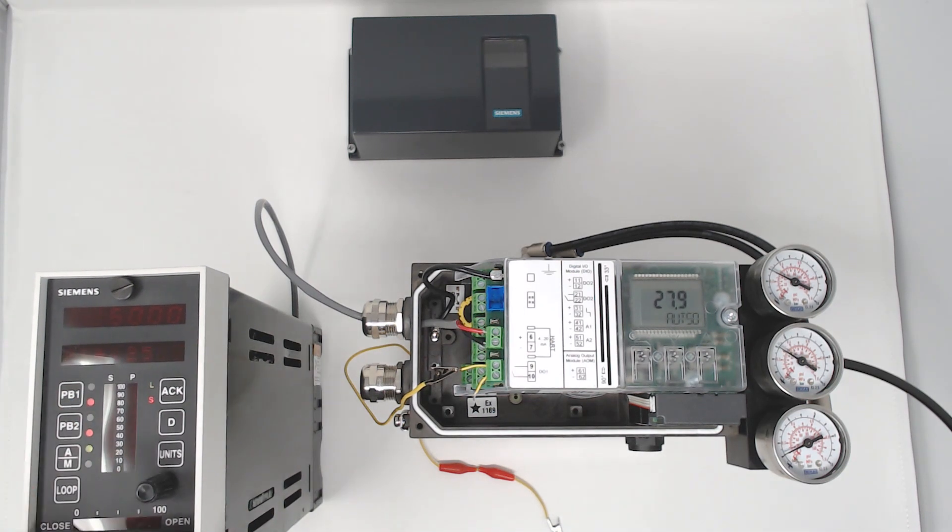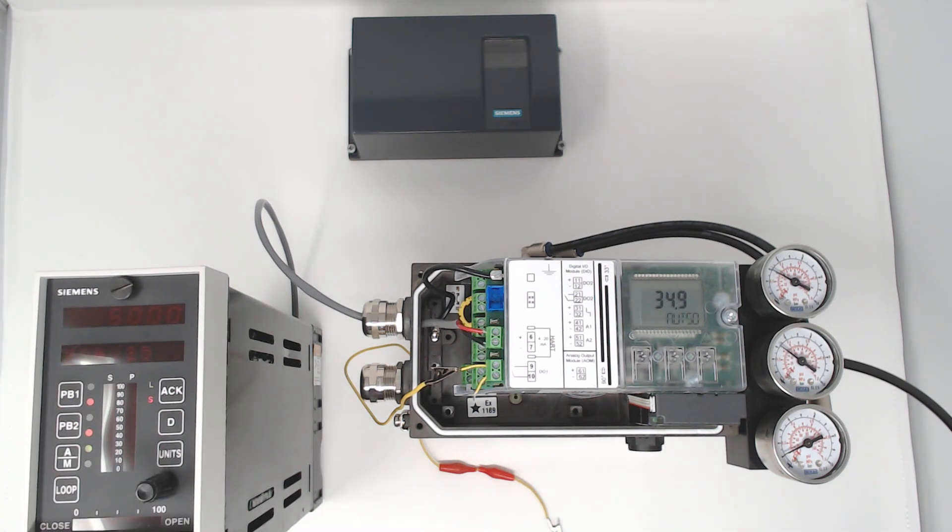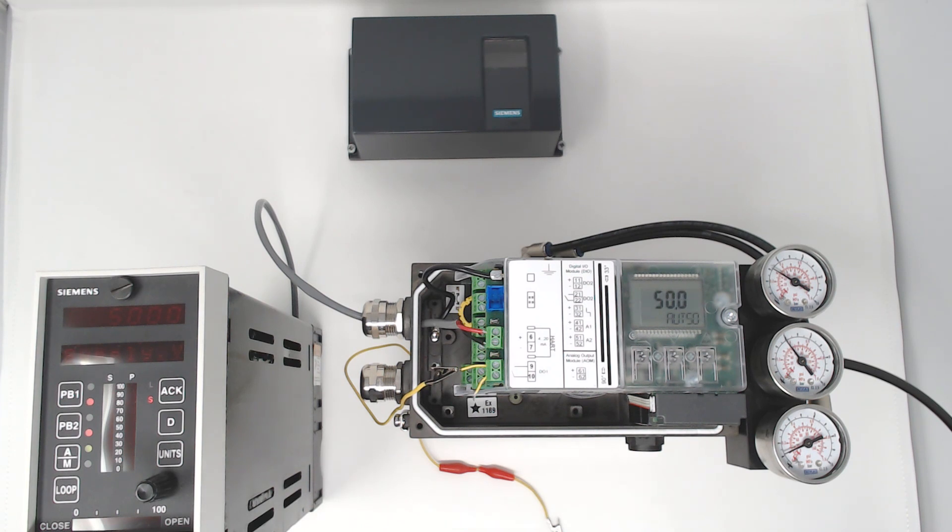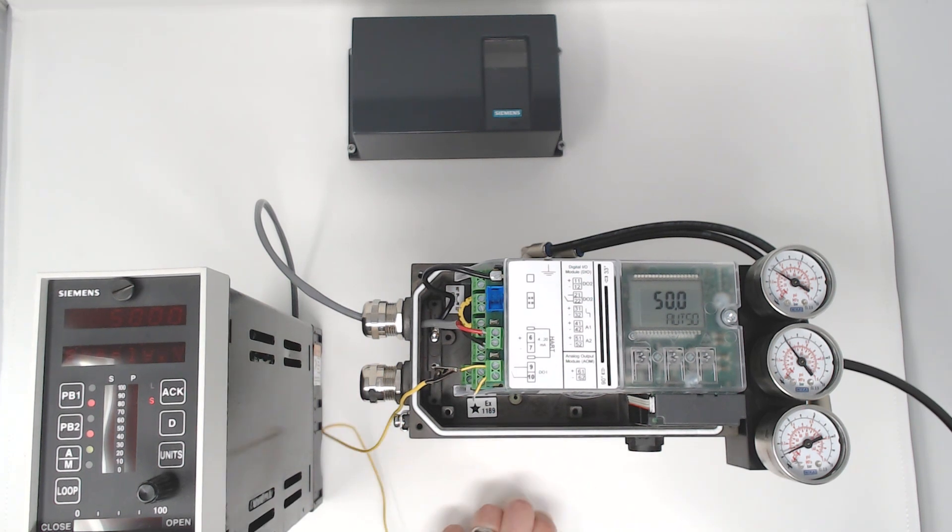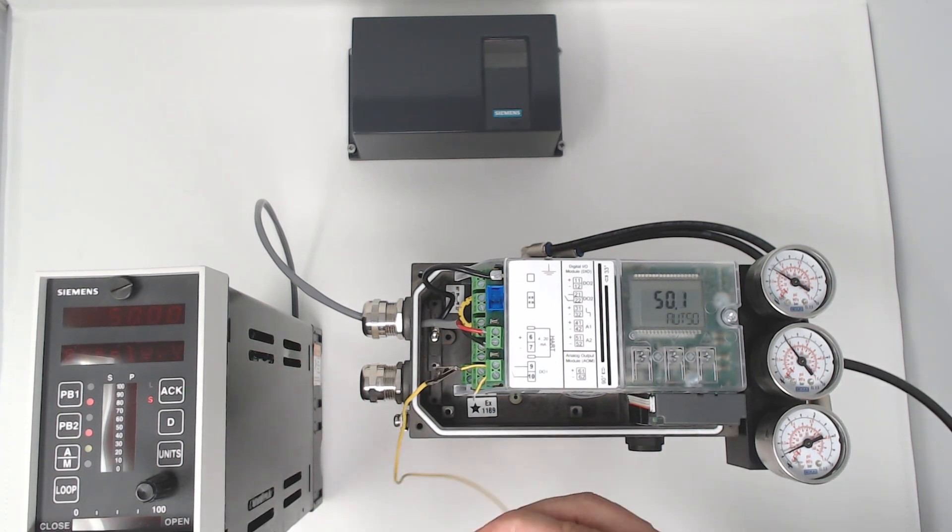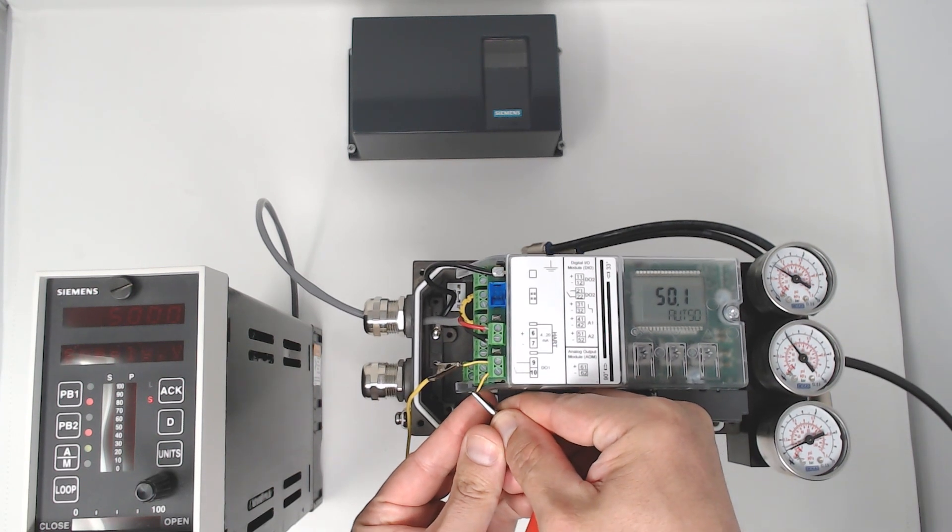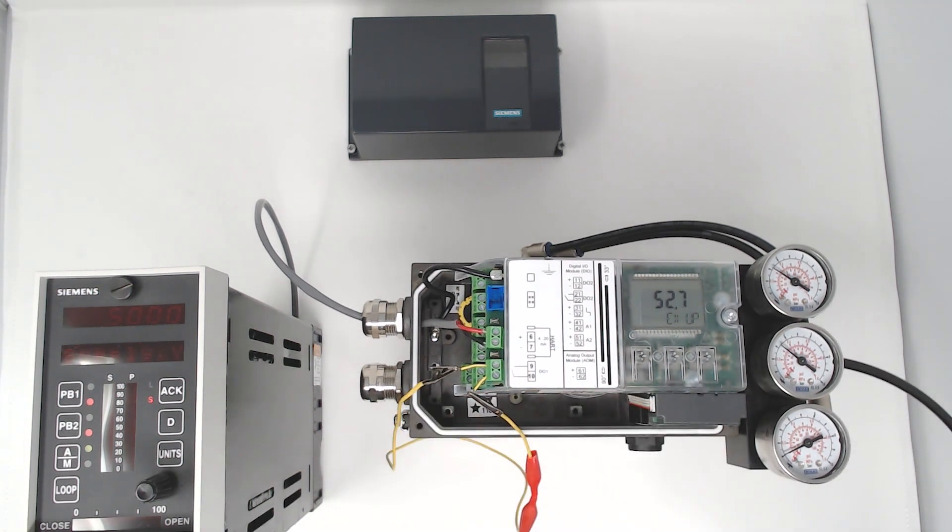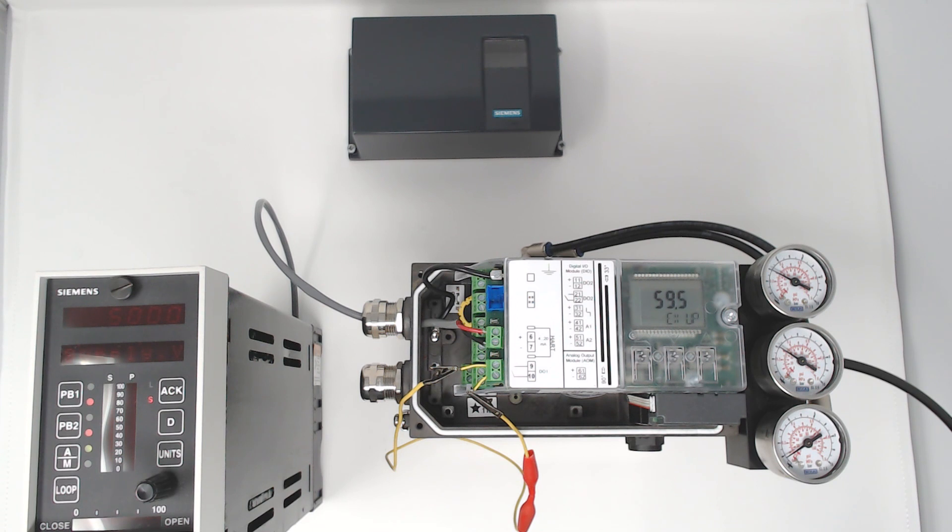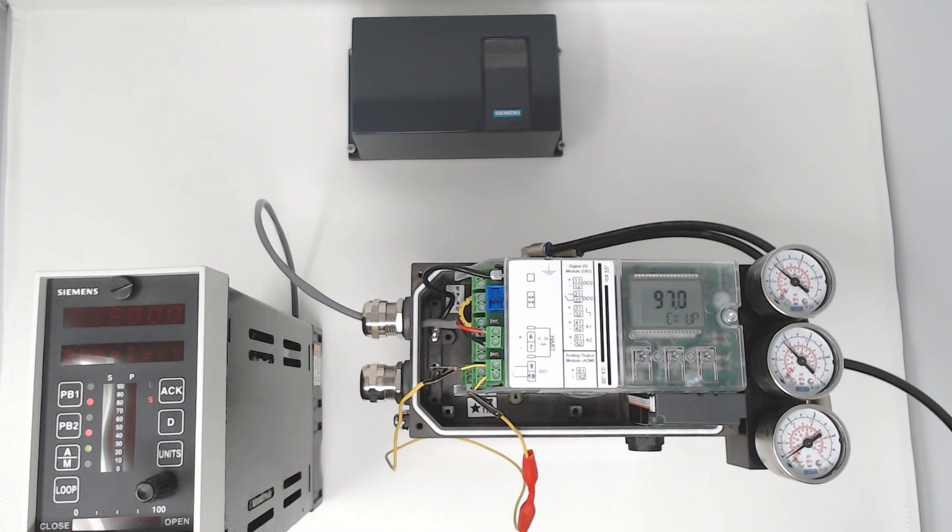Here I move the valve to 50% by the control signal and it's holding 50%. Now I'm going to trigger the input and it automatically drives the valve to the up position. The local display gives you an indication that it's an external up and it will stay in this mode theoretically forever as long as the input's triggered this way.